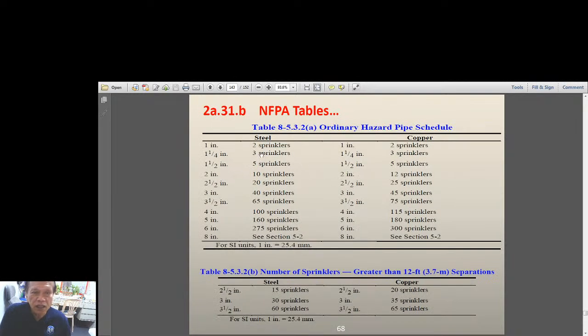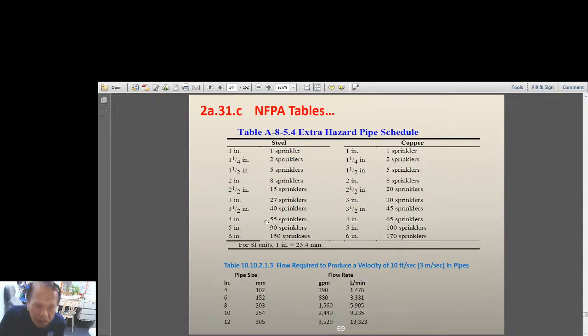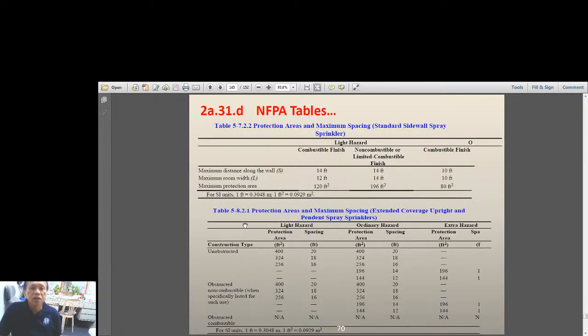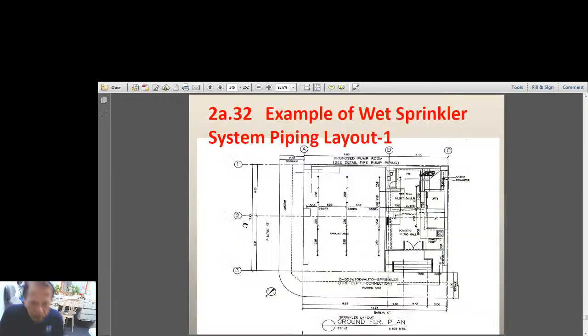And in the next slide, you will notice ordinary hazard. The 2-inch is 10 sprinklers, and now the 3-inch is 40. Initially, it is 60 sprinklers, but in the ordinary hazard, it has reduced the allowable number of sprinklers. Okay? Extra hazard, much lower, because the 3-inch is only 27 sprinklers, and the 2-inch is only 8 sprinklers, and so on. Okay? So that's how it is. And let me go back again to the chapter.